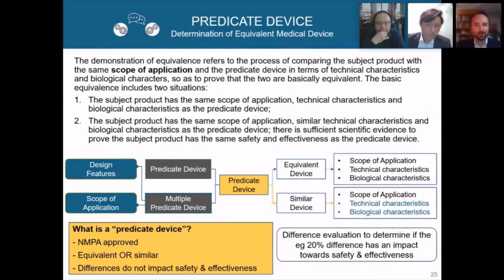Yes. Yeah. So to determine the predicate device, it needs to be NMPA approved. There needs to be one or more devices that are equivalent or similar, and the differences shouldn't impact the safety and effectiveness. You can find potential predicates by checking the NMPA website or the provincial NMPA website, or by market research. When choosing the predicate device for your China CER, the first requirement is that it must be approved by NMPA in China, as mentioned. Additionally, the predicate device should still be within its validity period. All devices in China must be renewed every 5 years in order not to lose their validity.